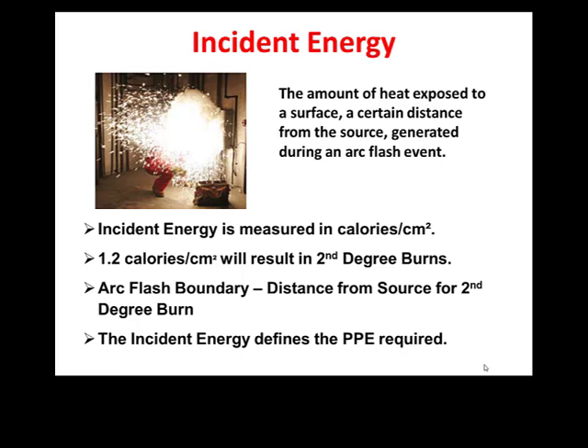Typically, the higher the voltage, the higher the incident energy. However, the clearing time for the overcurrent protection device, whether it be a circuit breaker or a fuse, also affects the amount of incident energy during an arc flash. The 2015 version of NFPA 70E recognizes that for voltages 120 volts or less, there is not enough energy to sustain an arc. Earlier versions of NFPA 70E used 240 volts or less.